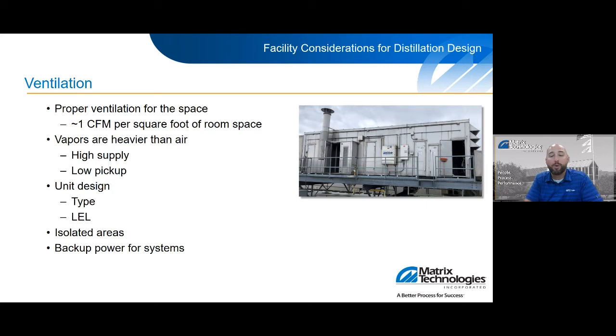Should the level exceed 25%, you need to make sure that your HVAC system goes into full exhaust mode and supplies with 100% outside air until you either resolve the problem or the levels are reduced. But even if the levels are reduced, it does behoove you to troubleshoot this system to figure out why you hit that level. Also, putting in isolated exhausts for certain areas.